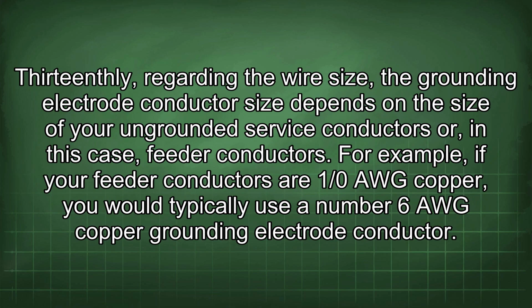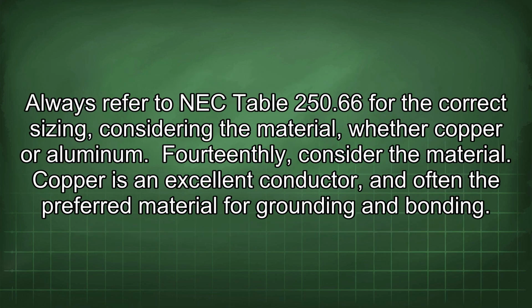13thly, regarding the wire size, the grounding electrode conductor size depends on the size of your ungrounded service conductors or, in this case, feeder conductors. For example, if your feeder conductors are 1/0 AWG copper, you would typically use the number 6 AWG copper grounding electrode conductor. Always refer to NEC Table 250.66 for the correct sizing, considering the material, whether copper or aluminum.